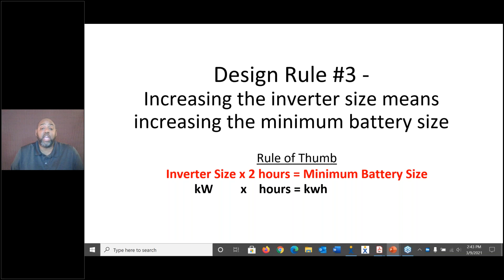So a quick sizing tip when sizing systems for your customers is just to think of it in that exact same manner: lithium batteries are designed to be discharged in a 2-hour window. So when I take my inverter, I'm not looking at the AC load, I'm looking at what the DC load would be on that inverter. So for instance, if we have a solar inverter that's 12 kW, the DC output on that is basically 8, and you take 8 times 2, which is 16, and that determines the minimum battery size that you will need. And I will further explain that later on.